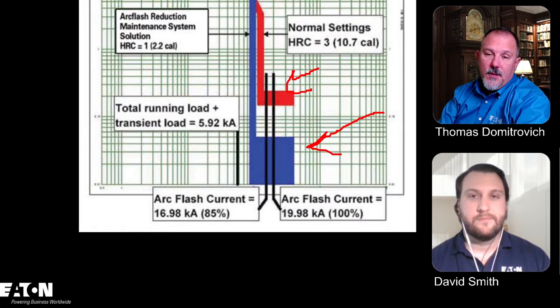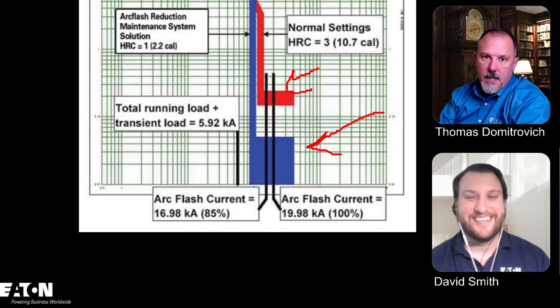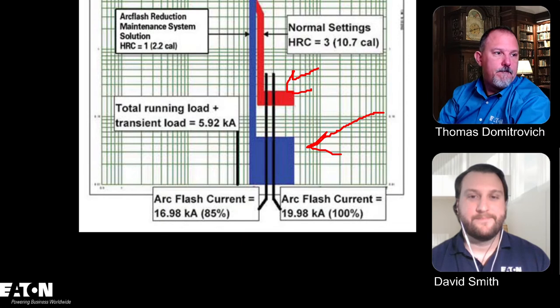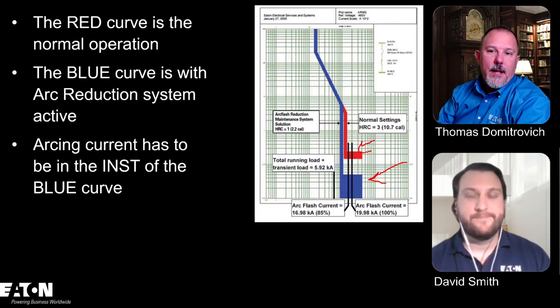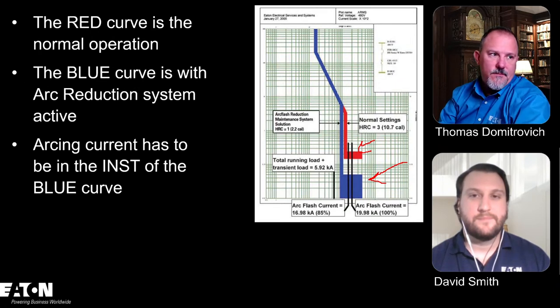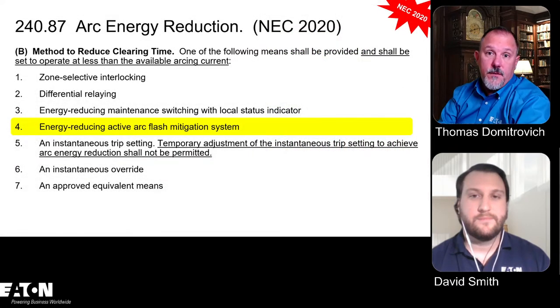Now here's another. Our time current characteristic curves show the clearing time at 0.04 seconds. You and I both know it operates much faster than 0.04 seconds. Yes, but we have a lot of conservative engineers in our company that love to add those delays because of frequencies. They may say, well, at 50 hertz it operates this way, and at these temperatures it operates that way, but they always put the worst case. Which is what you want, right? Yeah, and even a clearing time of 0.04 seconds is going to be a huge difference in arc energy. I'd rather be overdressed for that than underdressed.